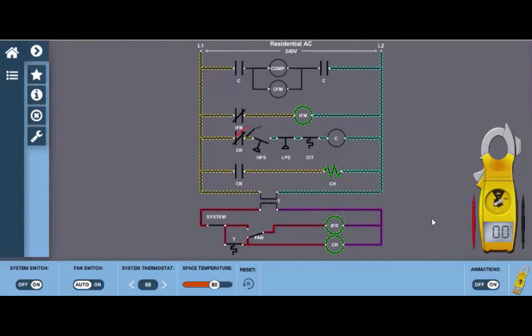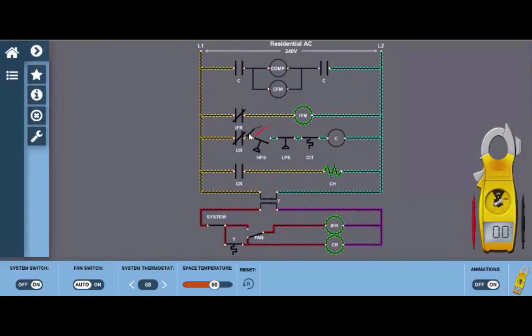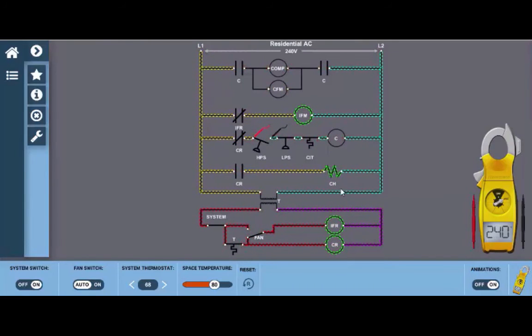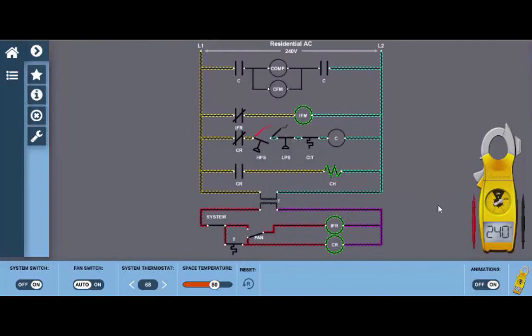Our next step is to move to the high pressure switch and if we move the leads across the high pressure switch, again if it's closed we should read zero volts. But in fact when we do this we can see we have 240 volts which indicates we have power into the contacts of the high pressure switch but nothing coming out. Again the meter is reading the difference in voltage here.